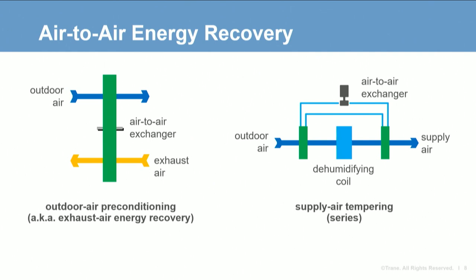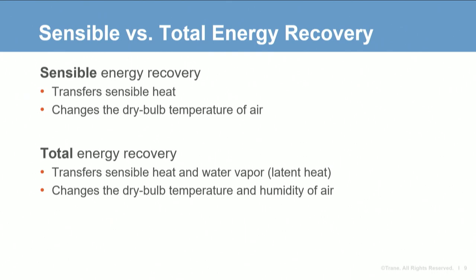For this program we're going to focus primarily on exhaust air energy recovery. Air-to-air energy recovery devices are generally categorized as either sensible or total energy recovery. Sensible recovery devices transfer only sensible heat, raising or lowering the dry bulb temperature. Total energy recovery devices transfer not only sensible heat but also water vapor, raising or lowering both the dry bulb temperature and the humidity ratio of the airstream.